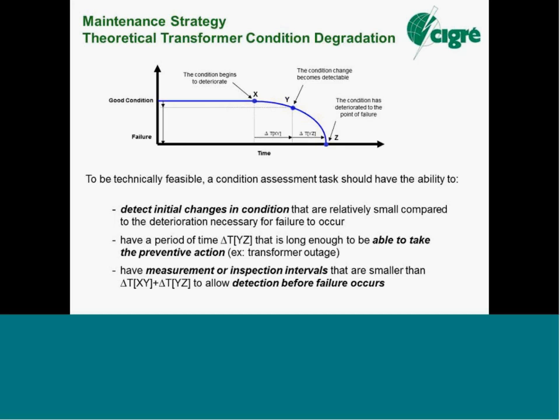They can have catastrophic failure. In the case of bushings, even an oil fire with total loss of the transformer, and maybe collateral damage to a nearby transformer, even the powerhouse, with the oil fire. So how far you go depends, for a particular transformer, on the criticality of the transformer and the consequences of its failure. And for the system that you want to purchase, is it comprehensive enough to detect lots of expensive failures?